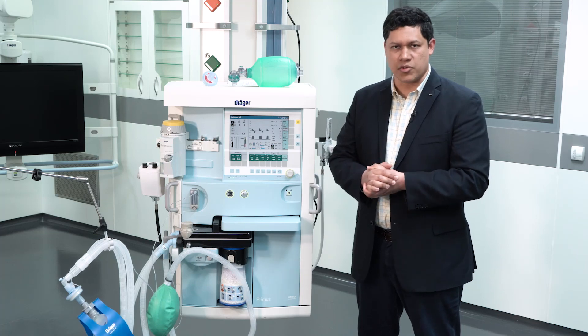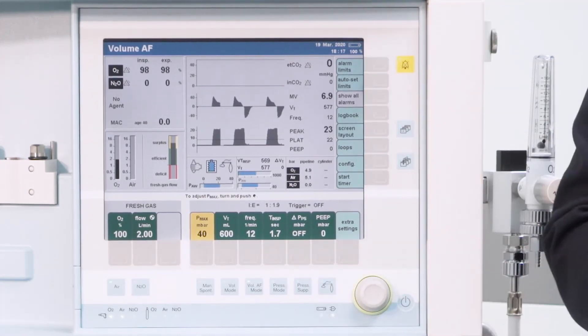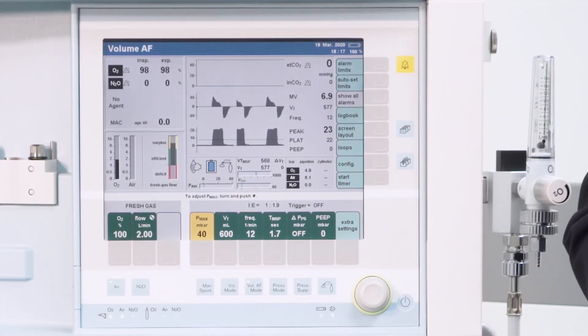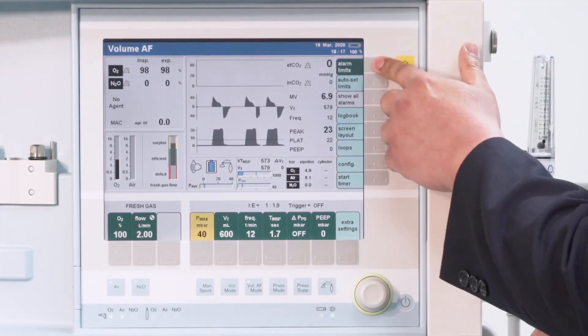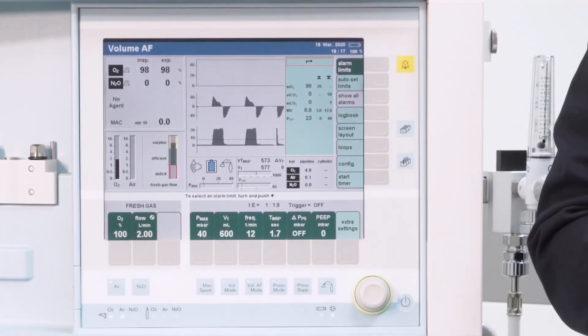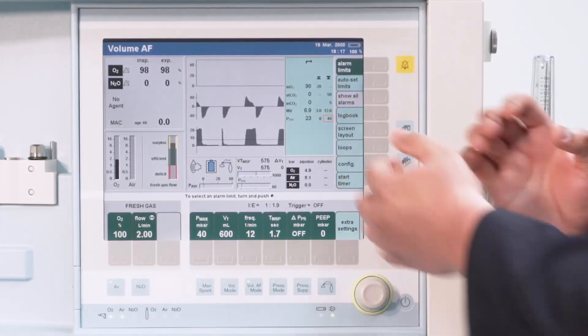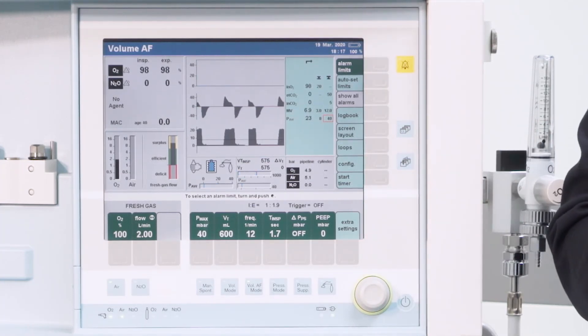In contrast, when using the anesthesia device, if we want to limit the pressure built in the airways of the patient, we have to use the Pmax setting. If we only want to set the limit for triggering the alarm, we go to the alarm configuration and set the maximum level of the alarm for airway pressure.